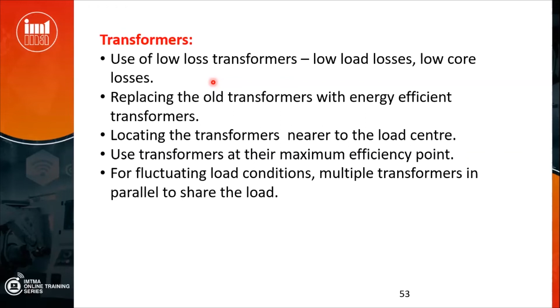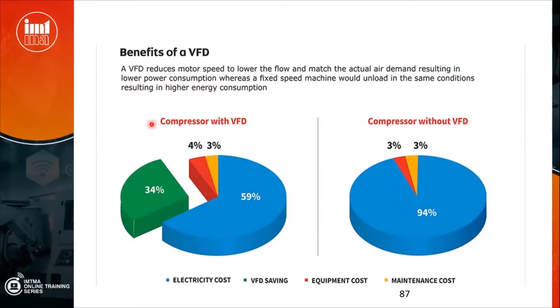by the transformer. See here, with VFD and without VFD, what is going to be the change? Compressor with VFD, compressor without VFD. See, where is 94% of this energy? Where is 59%? A VFD reduces motor speed to lower the flow and match the actual air demand, resulting in lower power consumption. Whereas a fixed speed machine would run only at fixed speed, would unload in the same condition, resulting in higher energy consumption. See here, this is the clear indication. So nowadays, we should never go for pumps or compressors without VFDs. That is the idea. The whole concept is shown here.